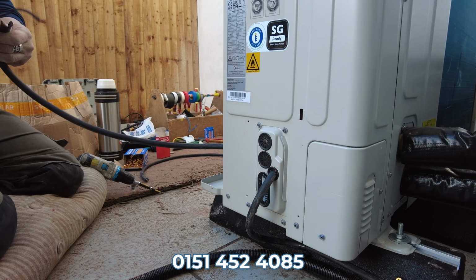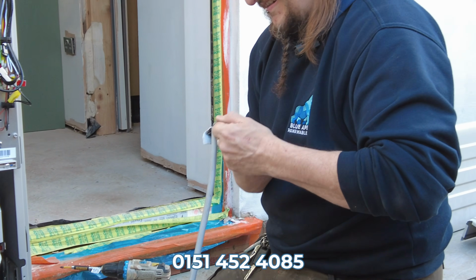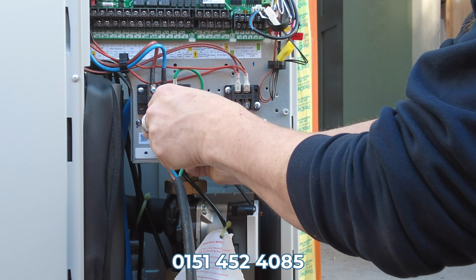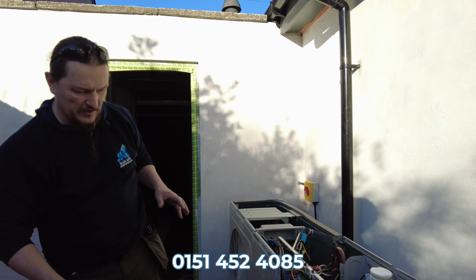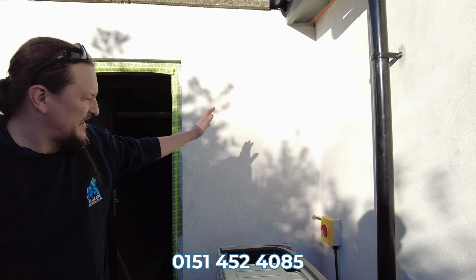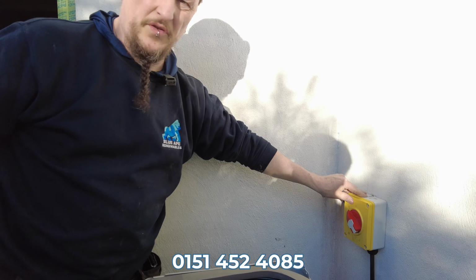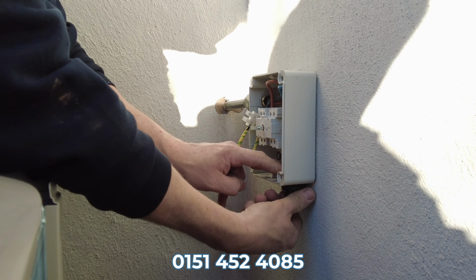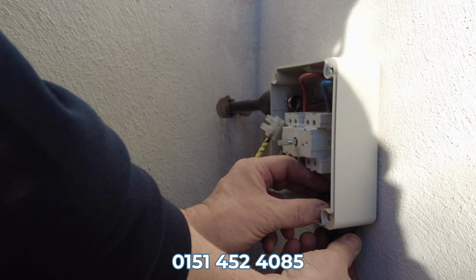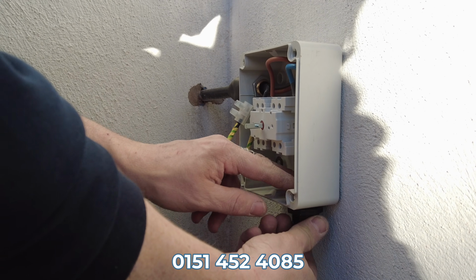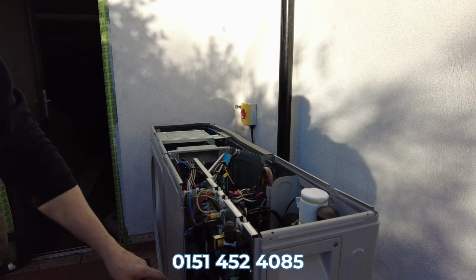We're now working on getting the power to the air source heat pump, and then we'll connect up all the control cables, the thermostat, various valves and actuators. This is the isolator for the air source heat pump. So this is the main power supply from the little board in there, fed by an RCBO that will come in and feed the pump.